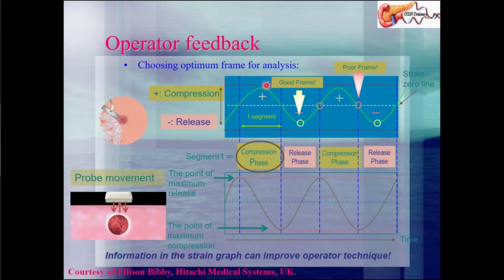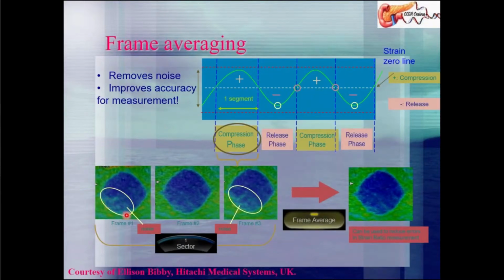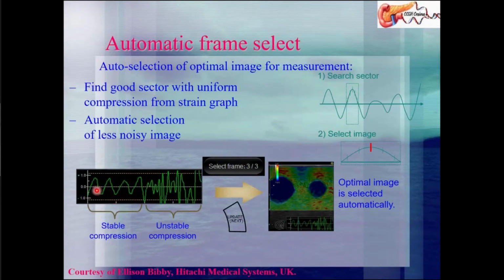When you get compression and decompression of the tissue, then you can move your pointer back and forward, and you can select a good frame for the elastography. And this is usually when you release the tissues, so during the decompression phase. Then you can average several elastography images, and you can get an average image, and then you get rid of some of the artifacts. This is how a stable compression looks like. So this is an optimal examination where you get stable compressions and you get this sinusoidal curve.